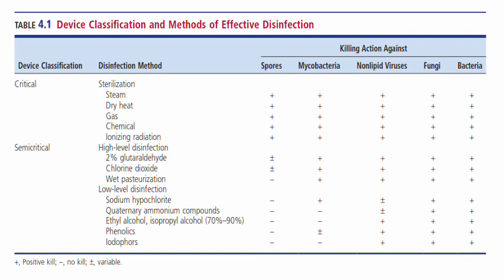Now, for critical devices, it is important that all types of microbial life are eliminated as these may pose problems to the patient. So, examples of disinfection methods for critical devices are the following: steam, dry heat, gas, chemical, and ionizing radiation. So all of these methods po for critical devices can kill up until spores. So they are called sporicidal. While your semi-critical naman po, the high-level disinfection for semi-critical devices are the following: using 2% glutaraldehyde, chlorine dioxide, and wet pasteurization are all types of high-level disinfection. And they are typically sporicidal except for wet pasteurization.